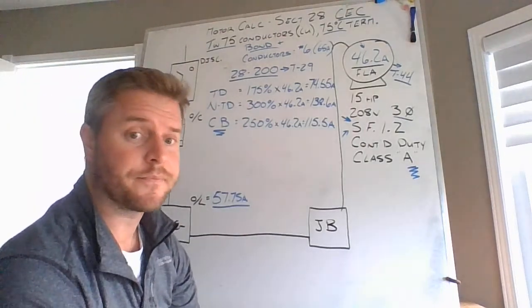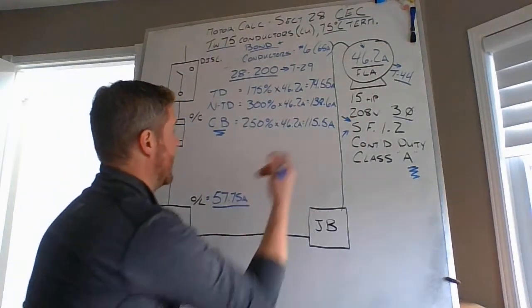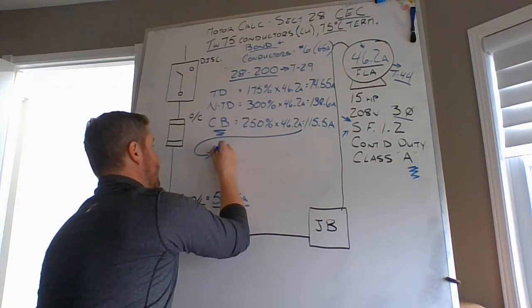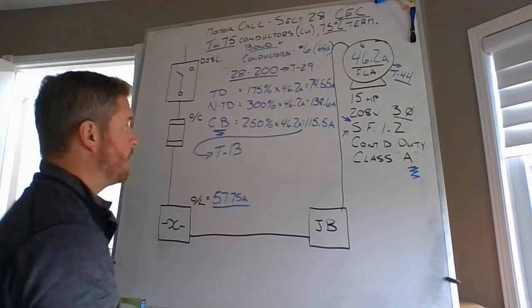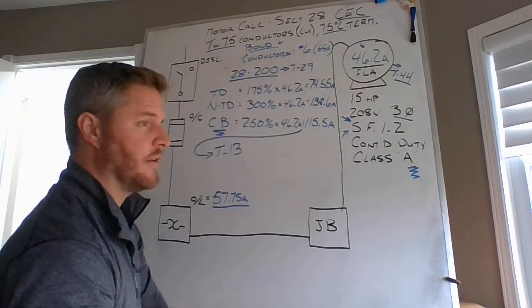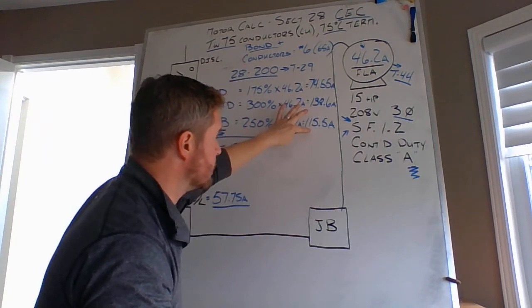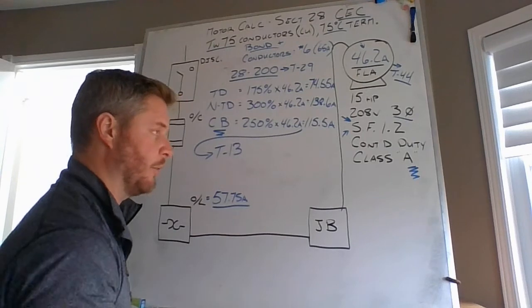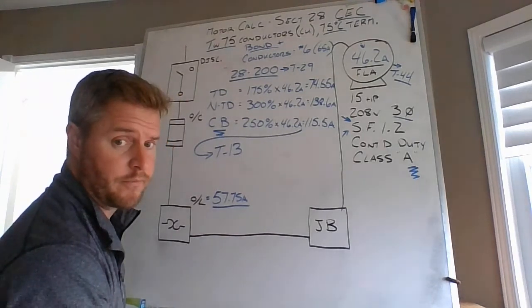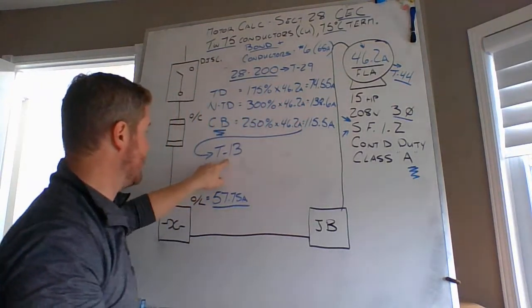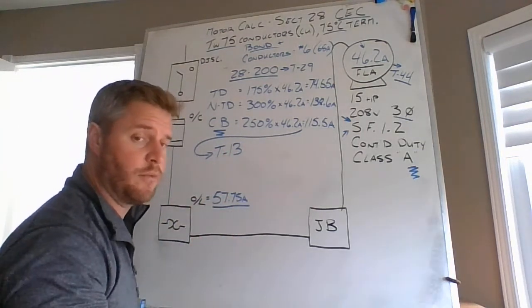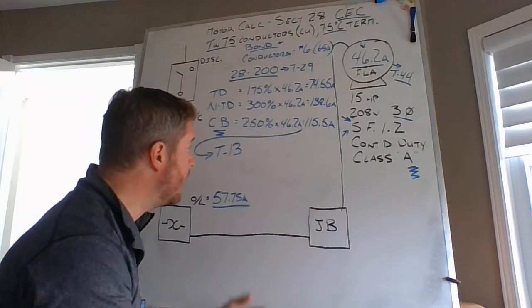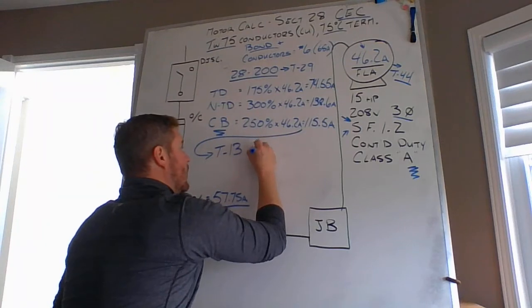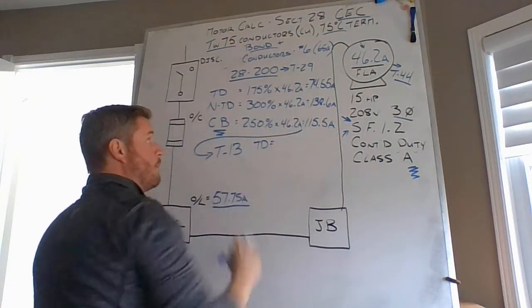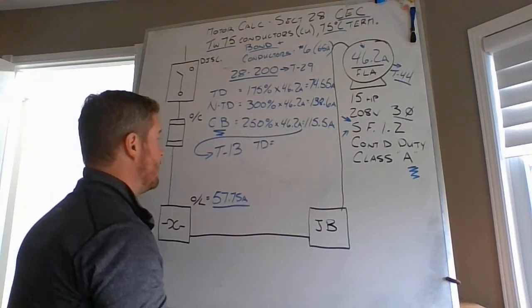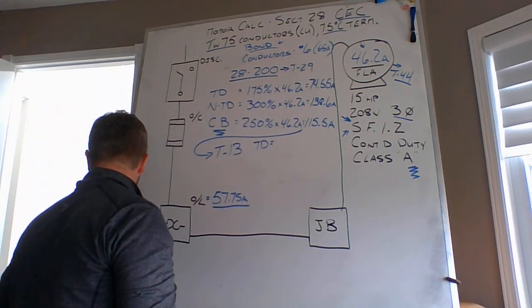So what do we do? Well, we do have a table in our code book that tells us the nominal installed sizes of fuses, and that's coming from Table 13. Table 13 will give us nominal installed sizes of fuses. However, I cannot exceed the values calculated based on my rules from Table 29, coming directly from 28-200. So I can take these calculated values and go to Table 13 to figure out the nominal sizes that the CEC recognizes for overcurrent protection. In that case, if I'm looking at a time delay fuse, I know that I can't exceed 74.55 amps. So I go to Table 13 and I should be allowed to install a 70 amp fuse.